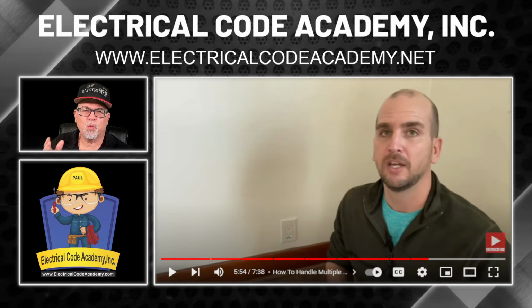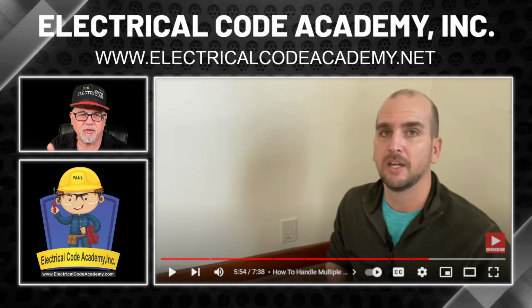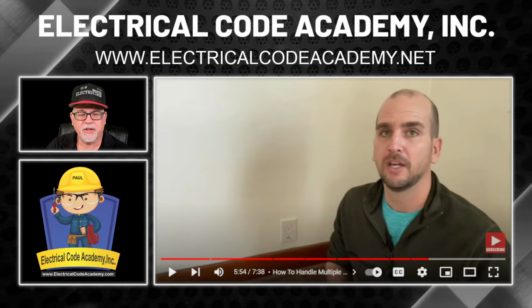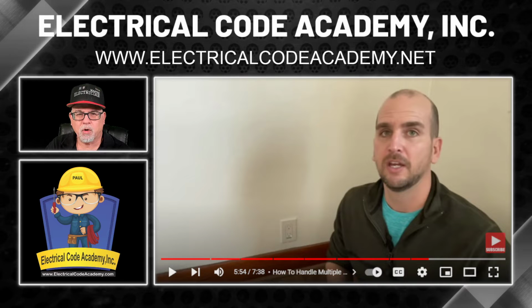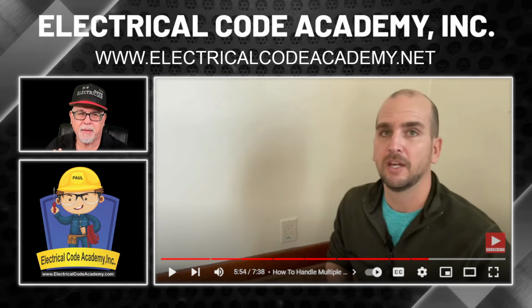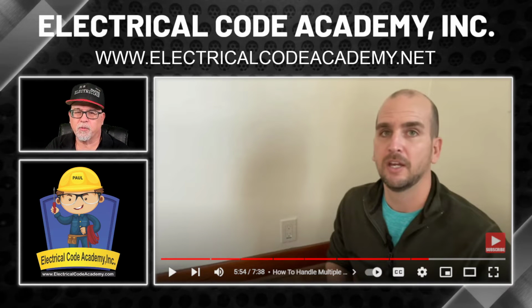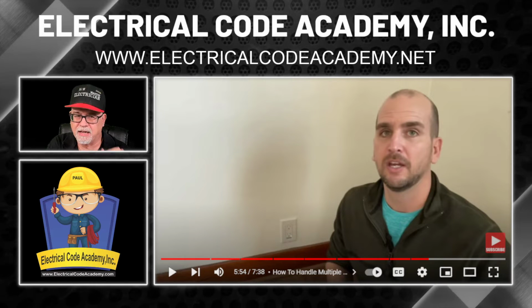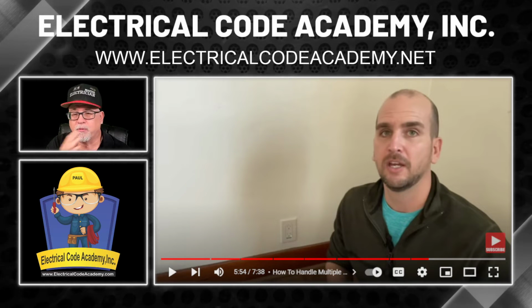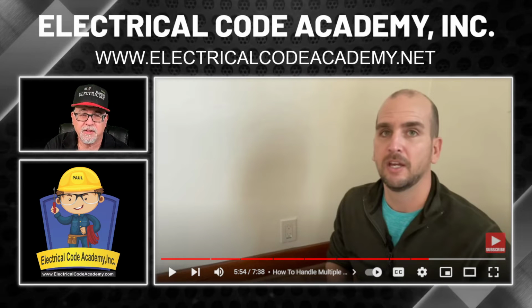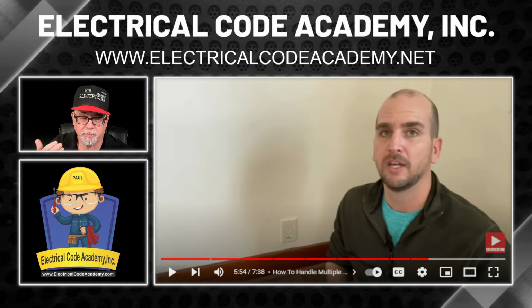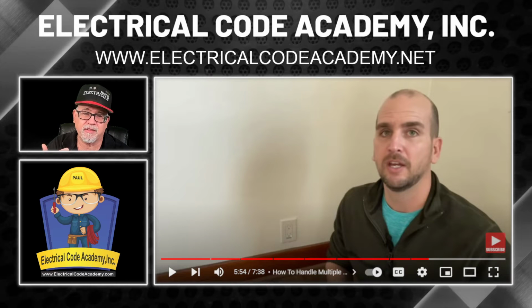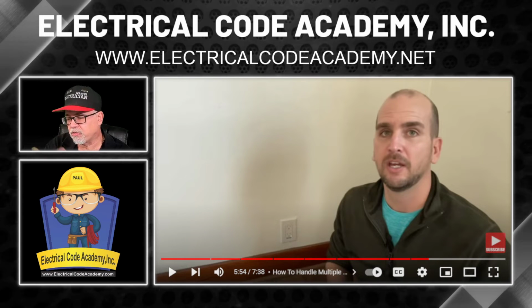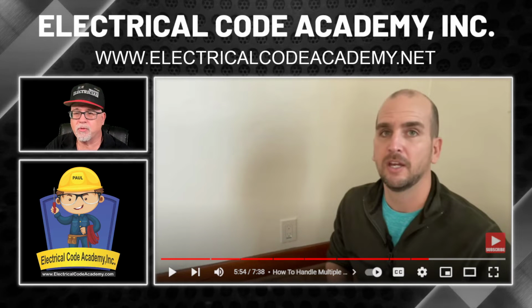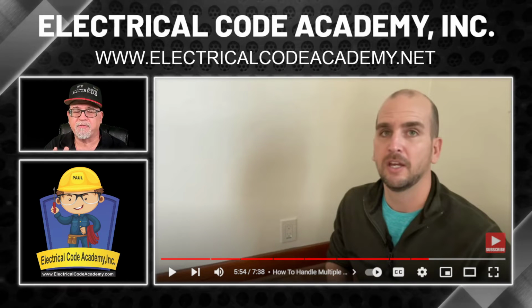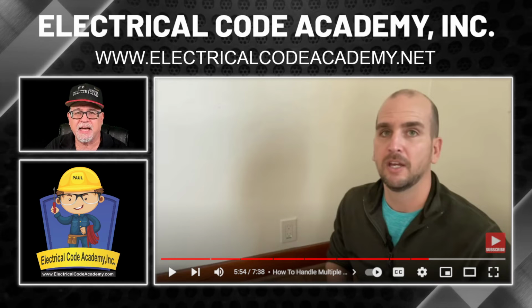So GFCIs work because they're looking for the imbalance of the current draw between the hot and the neutral. Typically, GFCIs work on what we call a 5 milliamp nominal, but the standard calls for it to be 4 milliamps or less, or 6 milliamps or greater. So at 4 milliamps or less, it will not trip. At 6 milliamps or greater, it will trip. So that is leakage current, not traveling back on its intended path. All the circuits travel through the toroidal coil in order to not create a magnetic field that can cause the action of the GFCI to function.